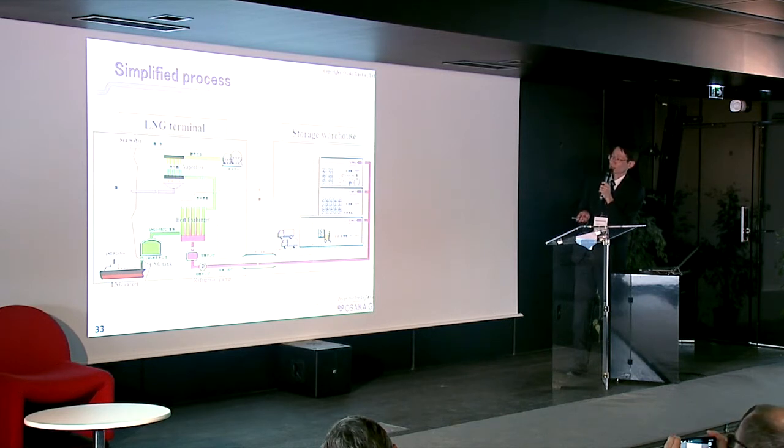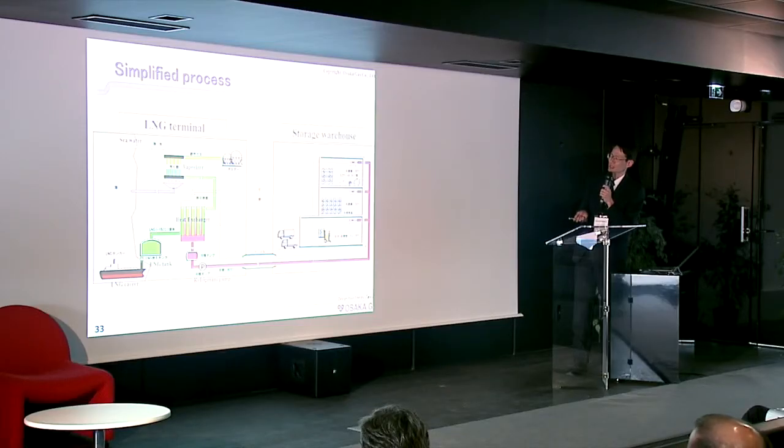And this is a cold energy warehouse system. Vaporizers are here, and the intermediate heat medium is chilled by energy, pumped up, comes to the warehouse, vaporizes, and returns to the condenser. So this system is expensive. So a lower utilization temperature is better for cold energy utilization.